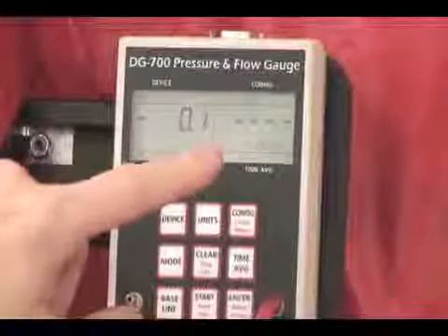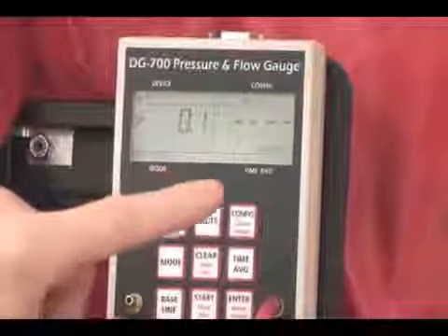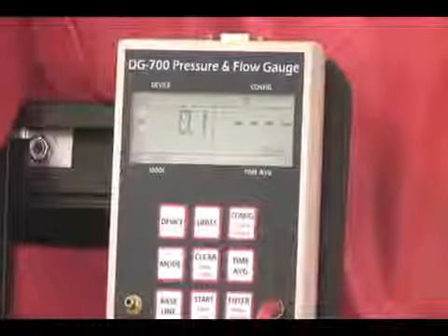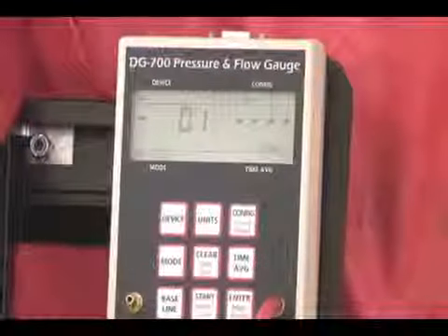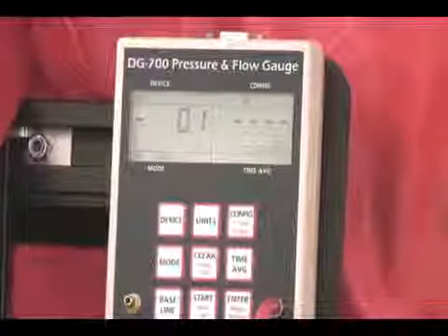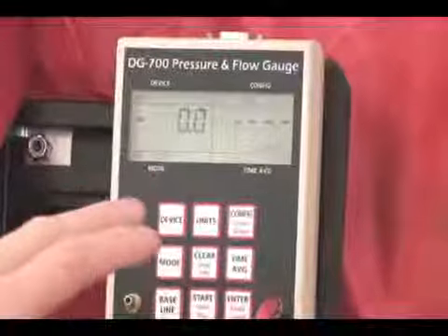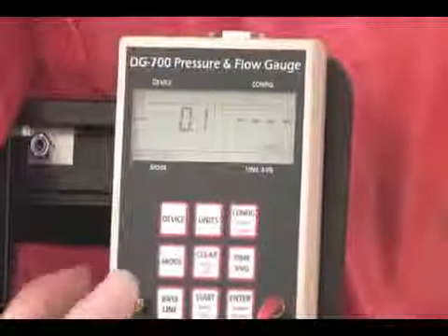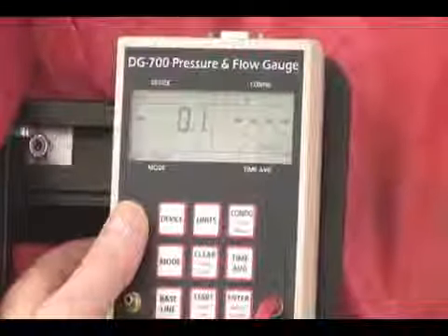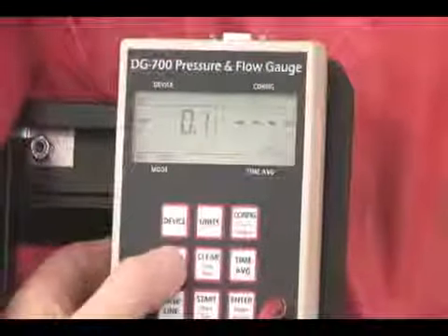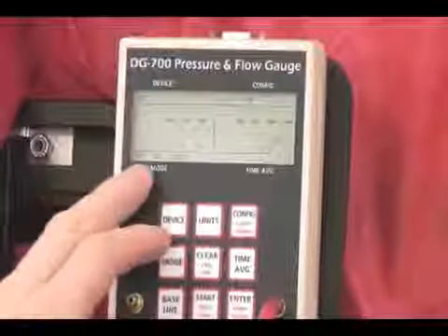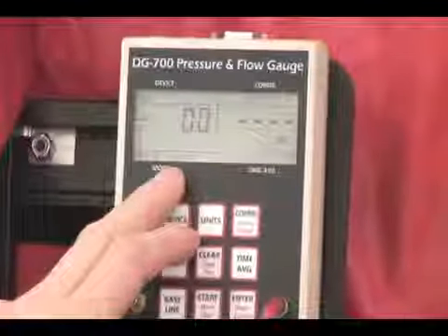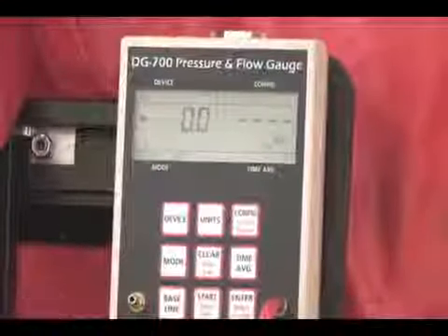This CFM at 50 pascals is an extrapolation mode that we'll show you later, where you don't have to achieve the exact test pressure. You can get an approximate test pressure, say 45 to 55 if you're trying to achieve 50, and this will mathematically extrapolate it to 50 pascals as if you were at 50 pascals. This is one that is very commonly used with blower doors. The next mode, pressure flow at 25 pascals, is much more commonly used in ducts, and we won't be going into it in this section.